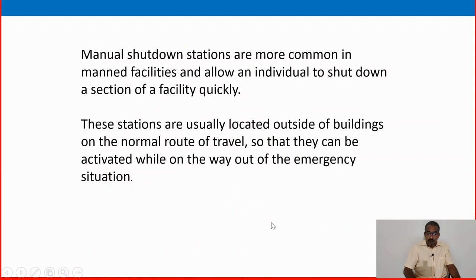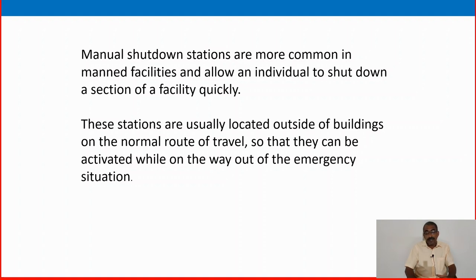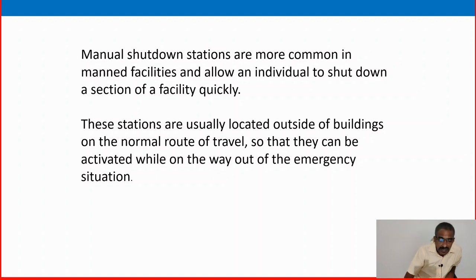Manual shutdown stations are more common in manned facilities and allow an individual to shut down a section of a facility quickly. Automatic shutdown systems are there, but ESD valves are also there. If instrument air pressure goes low-low, the entire plant will trip. Even though automatic shutdown systems exist, manual shutdown stations also provide an additional security feature for the oil and gas plant. Any operator, any control room person, or any responsible person can initiate a manual shutdown as well.